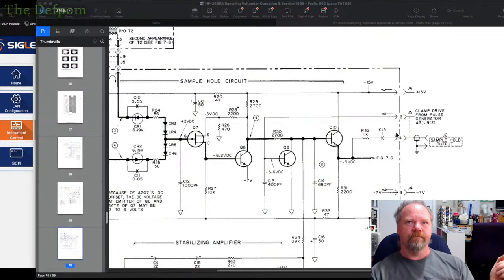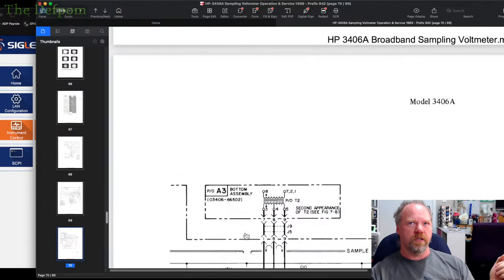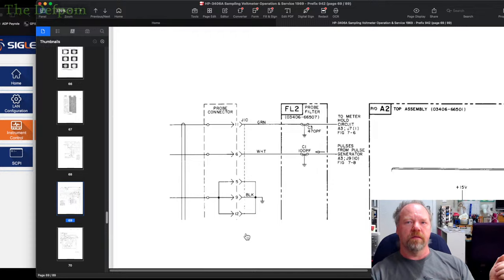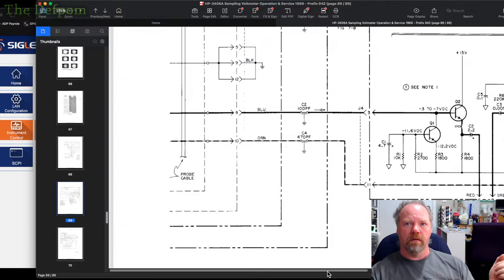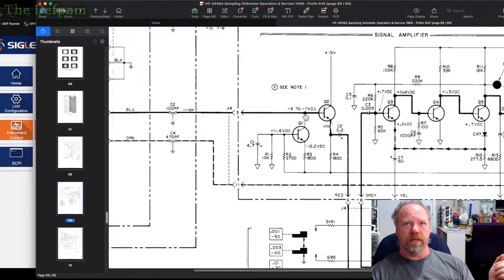but at least now I know what I should be getting. I've got some reference information about what should be there, so if it does come back, I've got a bit of a direction to go in. I know these voltages definitely change. They definitely go out of whack. Yeah, so the probe output changes, which is one of the interesting bits about that. So that test point was here. Right there. So I was getting, was it 4.6, negative 4.6 volts or something like that going in at that point, which is smack bang in the middle of that, basically, when it was working.